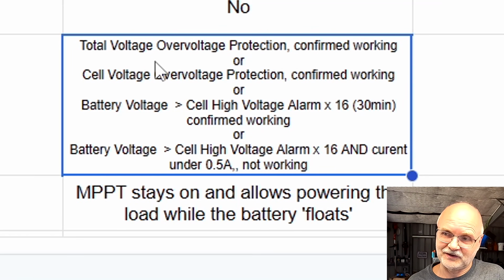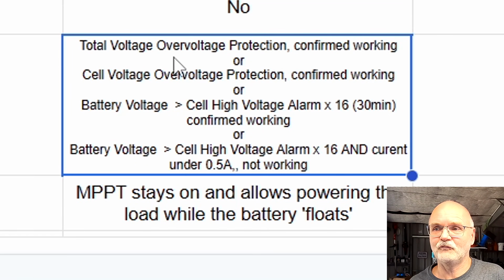And now we have 4 triggers which can actually reset the BMS to 100% state of charge. There is still the possibility to run into a total over voltage protection or into a cell over voltage protection, which either will then reset the BMS to 100% state of charge.